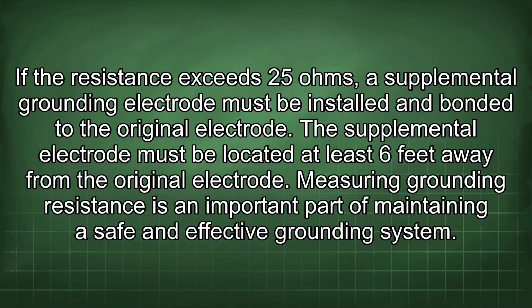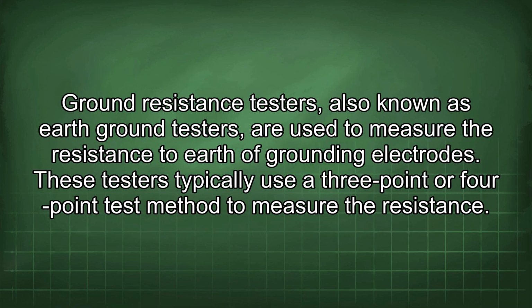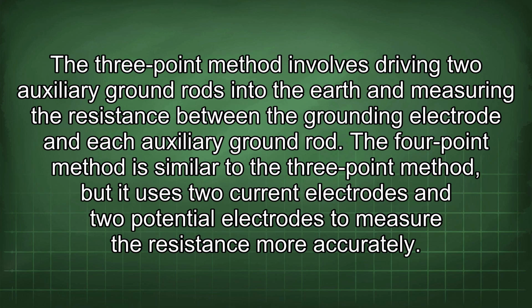Measuring grounding resistance is an important part of maintaining a safe and effective grounding system. Ground resistance testers, also known as earth ground testers, are used to measure the resistance to earth of grounding electrodes. These testers typically use a 3-point or 4-point test method to measure the resistance. The 3-point method involves driving 2 auxiliary ground rods into the earth and measuring the resistance between the grounding electrode and each auxiliary ground rod. The 4-point method is similar to the 3-point method, but it uses 2 current electrodes and 2 potential electrodes to measure the resistance more accurately.